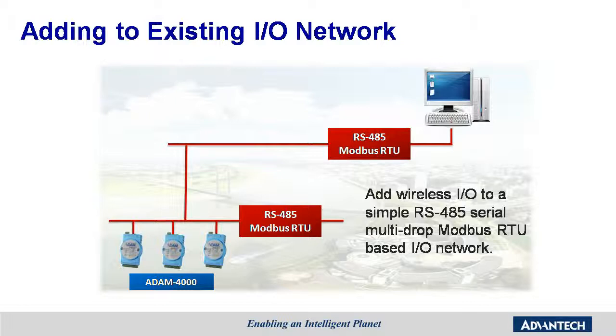Yeah, that's true, that's a really good point. This is a function of that Modbus RTU gateway, the ADAM 2520Z. It's a major feature of our ADAM 2000 family, and it allows the wireless network to be connected quickly and easily to an existing wired network using serial Modbus RTU protocol, typically on RS-485. Or the wireless network can also be connected directly to a control device like a PC or a PLC via RS-485 or USB, always communicating over Modbus RTU.